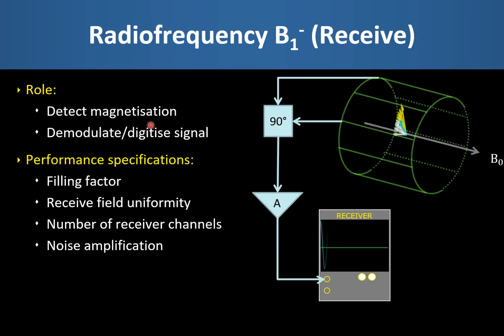The role of the radio frequency receive system, or B1-, is to detect the precessing transverse magnetization that induces the small voltage in the receiver coil. This signal is then amplified, as we can see here, in which case the precessing magnetization is dephasing in the transverse plane in the laboratory frame of reference, and we can see the typical free induction decay signal being shown here.